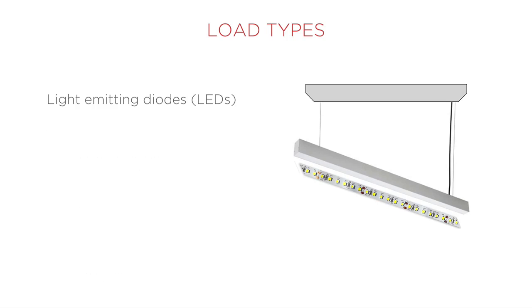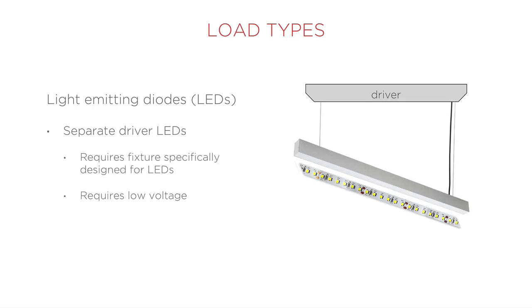LEDs fall in two main categories, separate driver and integrated driver. Separate driver LEDs are equivalent to fluorescent lights, or the separate ballast CFLs. It requires that the fixture itself has the driver internally. Separate driver LEDs require a specific fixture type, require low voltage, and follow the same guidelines as fluorescents and separate ballast CFLs.